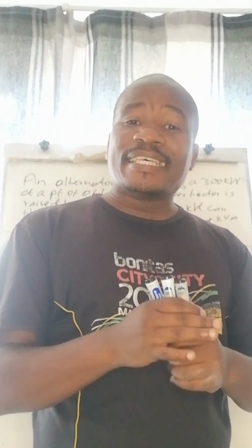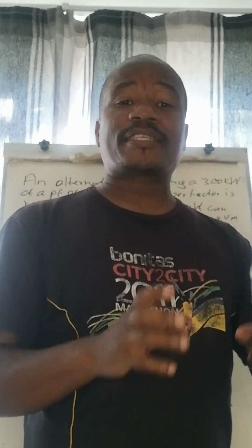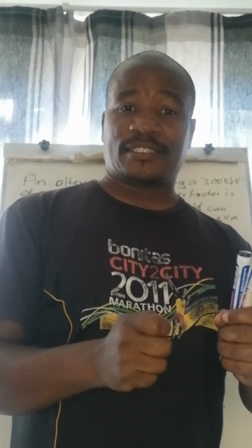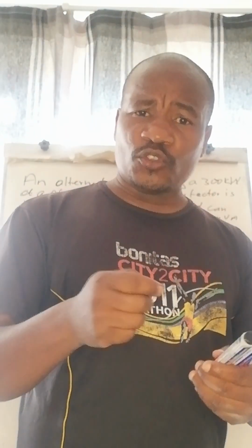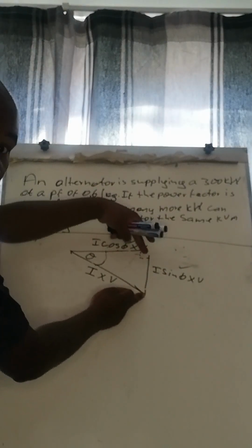And to improve that power factor, normally the static capacitors are connected in parallel with the load, such that they neutralize this reactive component of current.